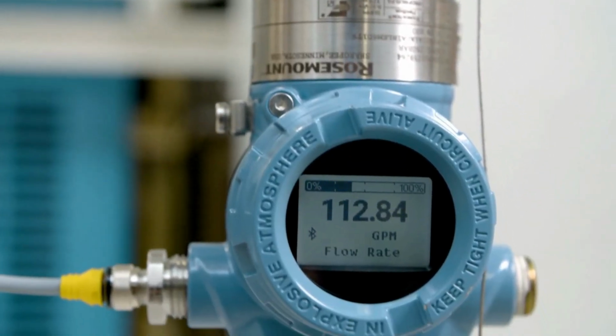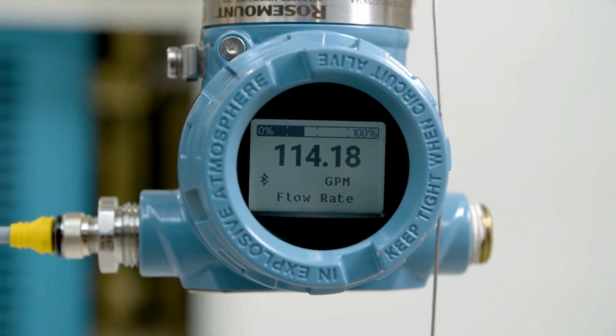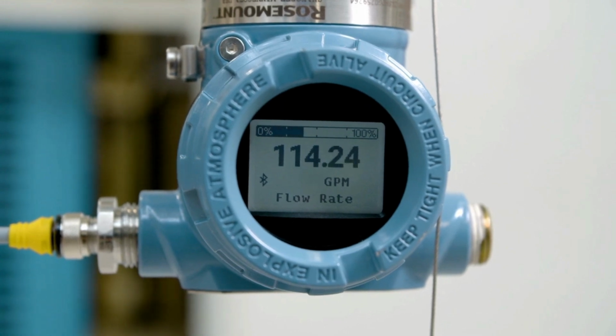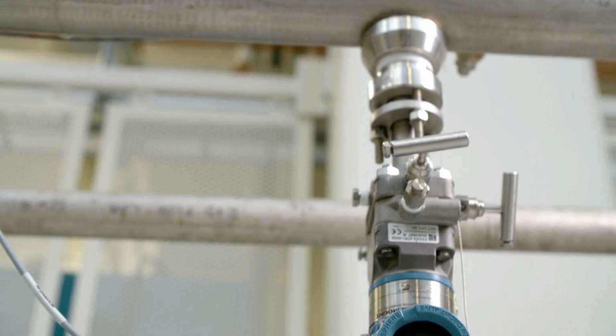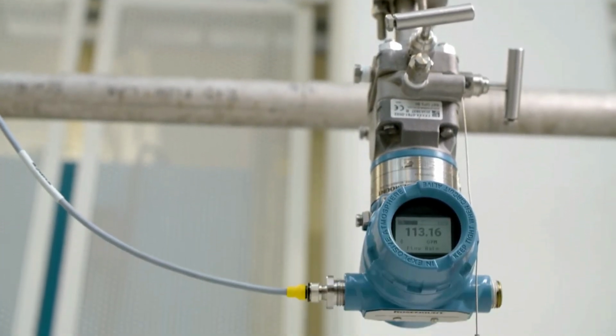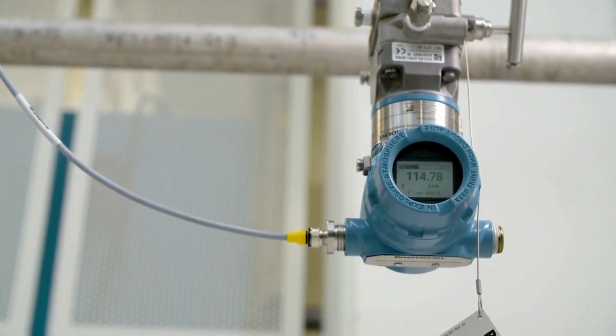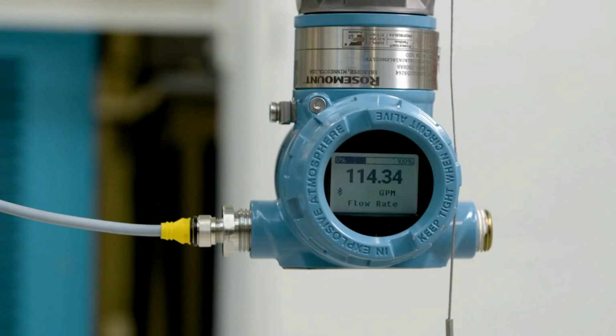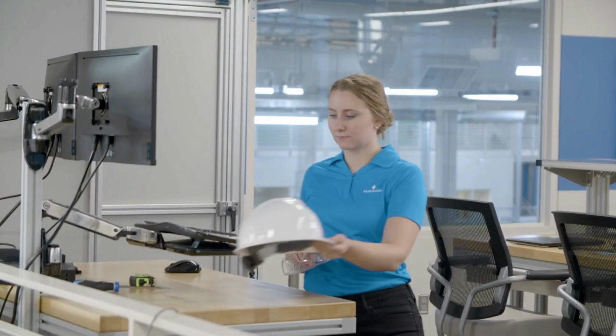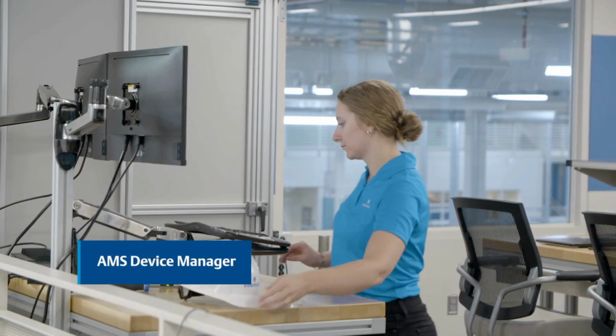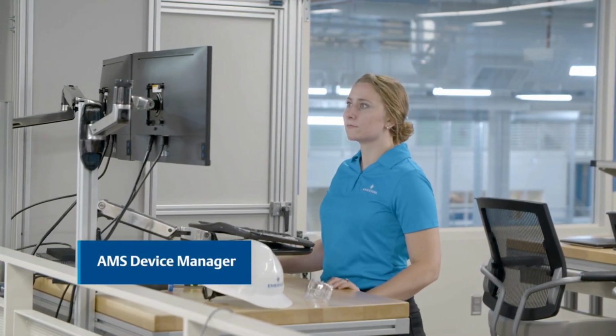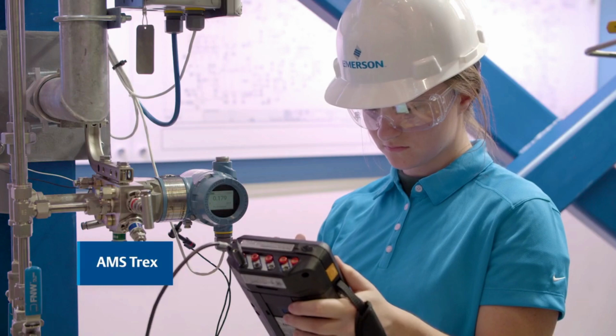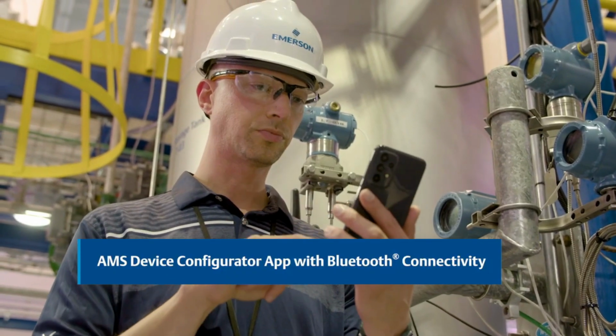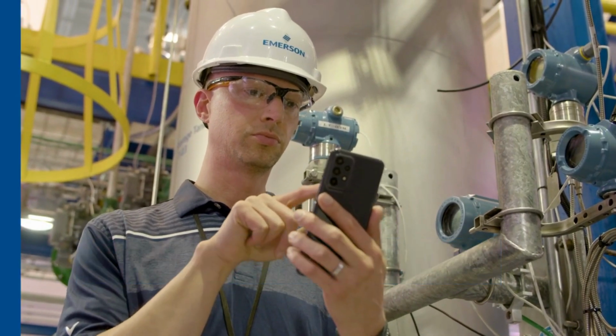Commonly, differential pressure transmitters are used to measure flow through the square root relationship. Historically, this method has been cumbersome and prone to configuration error. Flow-specific configuration provides an easy way to set the device up to output flow rate or flow rate with totalized flow. The transmitter can be configured for a flow application using any HART host, such as AMS Device Manager, AMS Trex, or the AMS Device Configurator app with Bluetooth connectivity.